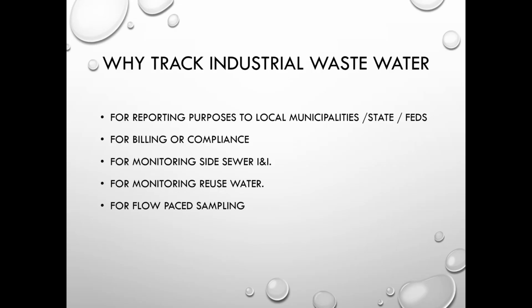So why do we track industrial wastewater? There are several different reasons. Most of the time, it's for reporting to your local municipality, state, or federal government, for billing and compliance. Many industrial facilities, rather than being billed on water in, would like to be billed on flow out. Incidentally, a lot of times this helps to identify side sewer infiltration and inflow. It also allows them to monitor water reuse. Another requirement a lot of times is flow-paced sampling rather than a time-based sample, so a flow meter will trigger the sampler.